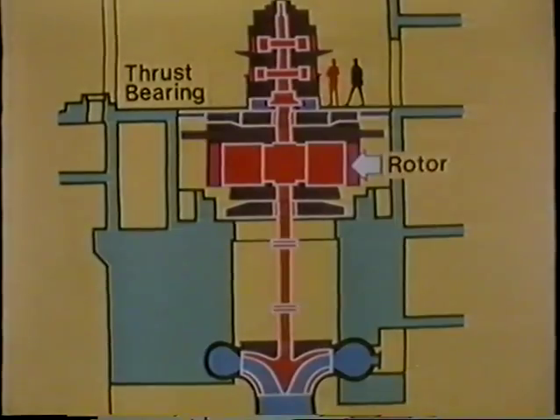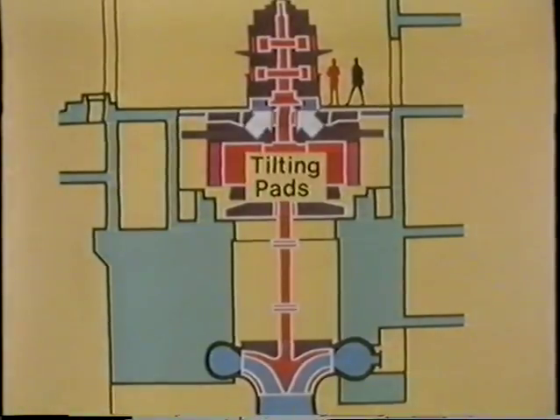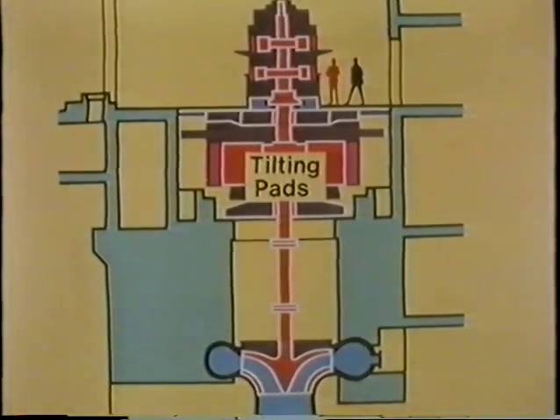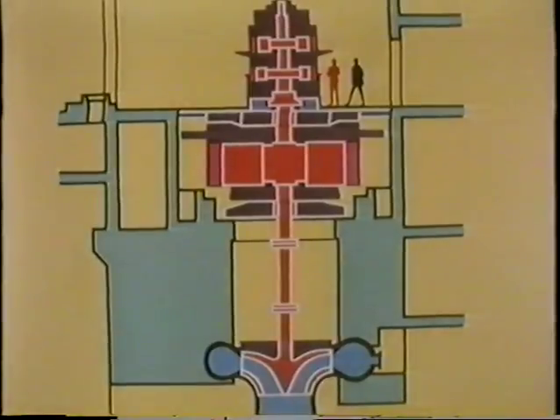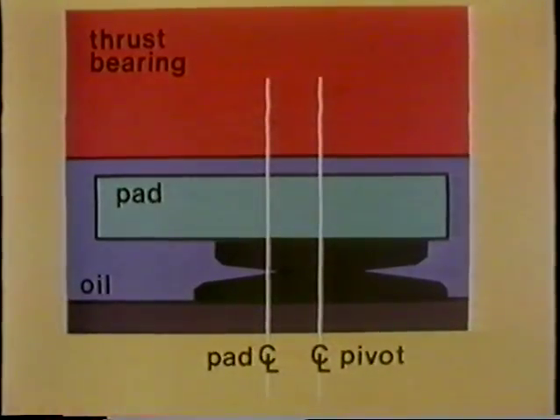It is fitted above the rotor and supports the weight of all rotating parts as well as the hydraulic thrust, a maximum load of approximately 200 tons. In non-reversible machines, the pivot is normally arranged behind the geometrical center of the tilting pads in order to obtain an oil wedge.